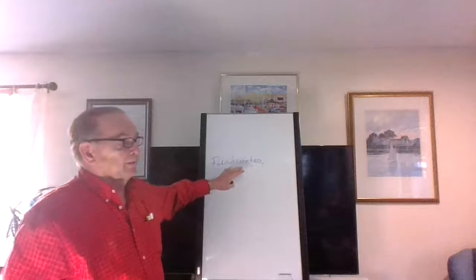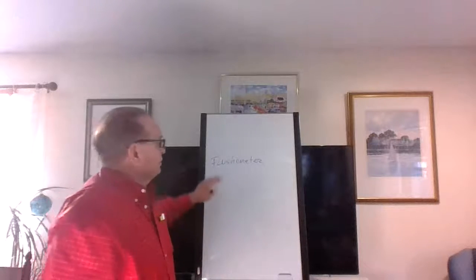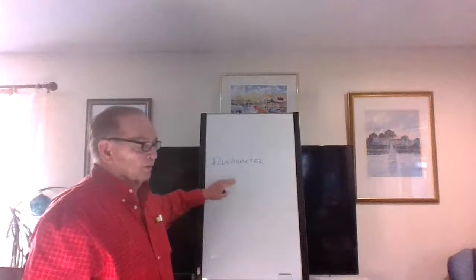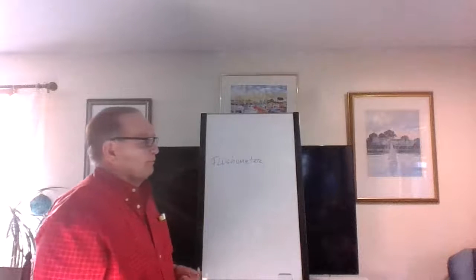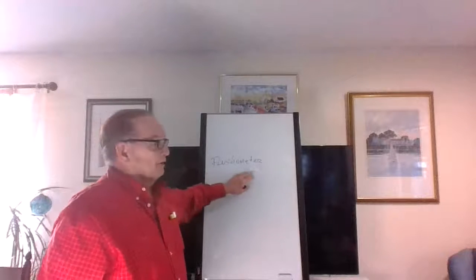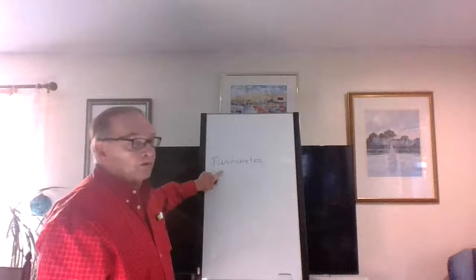The only thing is they need a lot of water. Never seen it in a private home. You would need at least a three-quarter water supply, if not one inch. Usually it's in a commercial building and they spell out exactly what you're going to put in as far as drain piping, venting, water piping. I've done one, but it's not half inch. You probably don't have enough water in a private home to make one of these work. These require a lot of water all of a sudden because there is no tank.